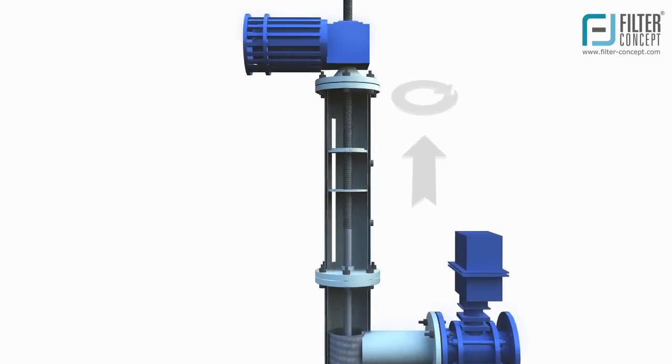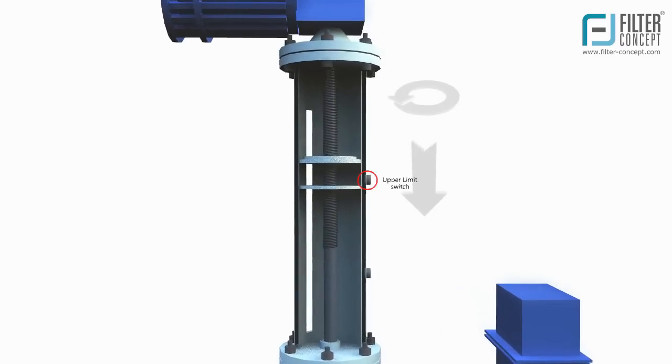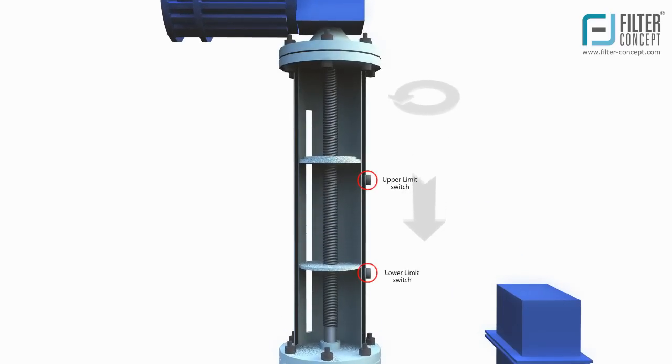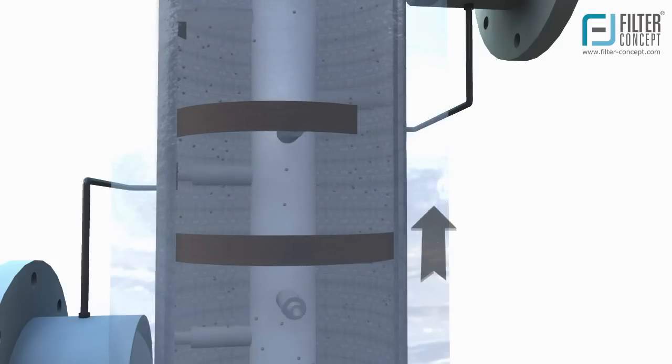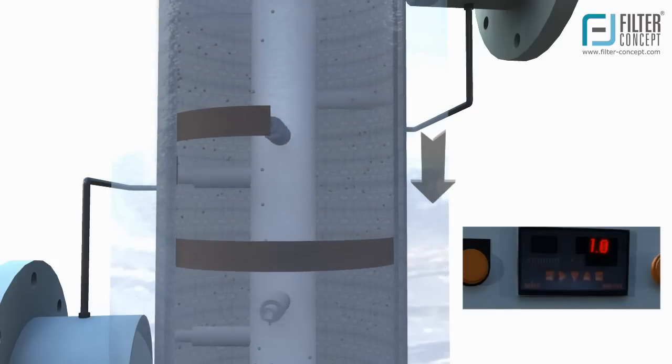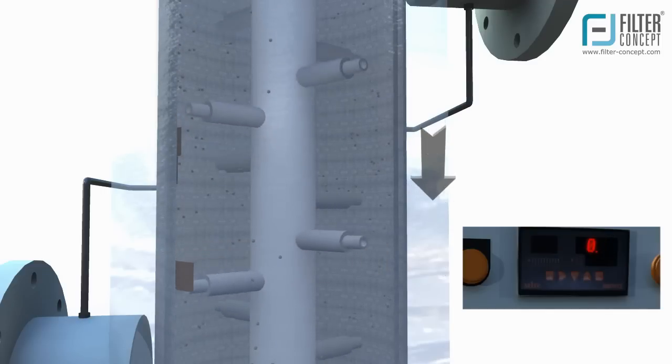The center pipe rotates with the help of geared motor at defined speed. It rotates inside the surface of filter element, and moves upward and downward to ensure proper cleaning of filter element throughout the area.